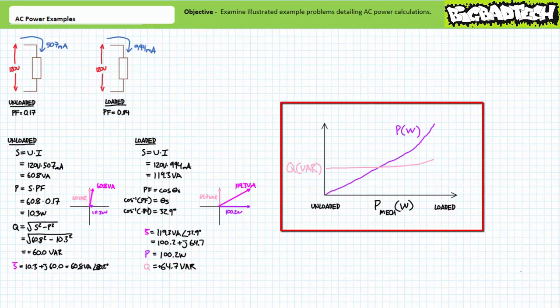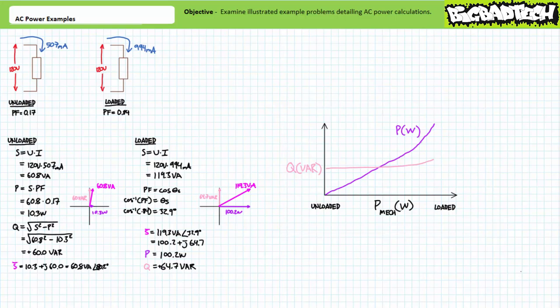A plot of real and reactive power input on the vertical axis as a function of mechanical power output on the horizontal axis illustrates this behavior quite succinctly. As mechanical power requirement—that is, doing real labor—increases, the reactive power requirement remains relatively constant across the entire range.